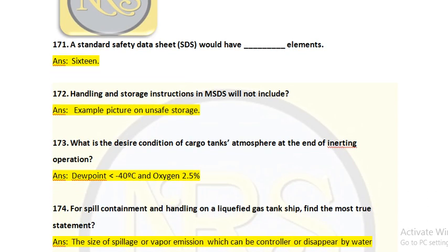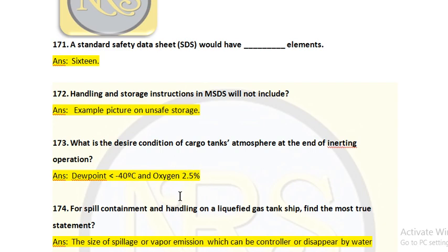Question number 173: What is the desired condition of cargo tank atmosphere at the end of the inerting operation? This is very important when taking first-time bunkering, delivery, or after dry dock. You pass dry inert gas — specifically dry nitrogen — not liquid nitrogen, because of the dew point factor. There should be no dew point in the system. As per IGF Code, the dew point should be less than minus 40 degrees Celsius and oxygen content should be a maximum of 2.5%.